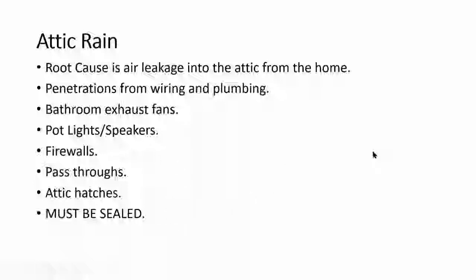People started to call this attic rain, but with the way that the winters have been going the last 5 years or so, with the cold week or 2 weeks, and then we warm up back to +5 or 0, and then we go back down. All these temperature cycles seem to have really exacerbated this problem. So attic rain essentially is a buildup of condensation as frost underneath the roof deck. And then when we do see that temperature warm up, it will literally rain in the attic.